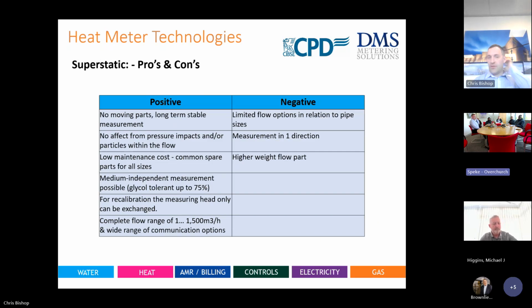Positives and negatives again, let's go through some points. The static principle is based on no moving parts, long-term stable measurement, just like the ultrasonic. It's a static principle, a no moving part meter. It's class 2 approved, with no effect from pressure impacts or particles within the flow. In comparison to the ultrasonic, if you have particles inside the system, they can be bounced and seen on the transmitters. This is not really seen by the main measuring head, because 90% of the flow is not seen by the meter in question. It's just that venturi that's causing that bypass pressure.